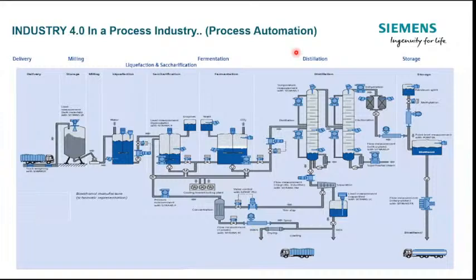For example, for closing the V1 itself, we may have more than 20 to 30 inputs or status or signals we need to check. Similarly, for switching on one motor, we need to check more than 20 to 30 parameters or 20 to 30 inputs from the field.